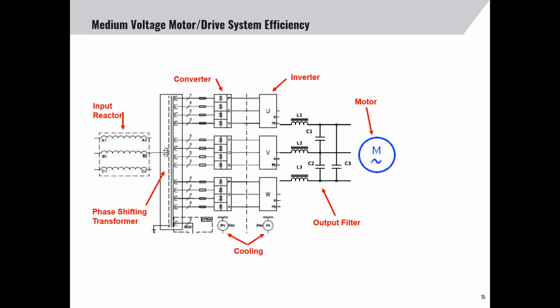Unlike motors, most adjustable speed drives are mounted indoors. Like motors, most of the efficiency losses are in the form of heat. Therefore, the heat loss from your adjustable speed drive must be dealt with to keep the equipment from overheating and potentially failing. Some of the common methods to deal with this heat include using water cooling, air conditioning, or large heat exchangers. Now, each of these methods has advantages and disadvantages, but they all require power to operate and thus should be considered in the total life cycle costs. There are some manufacturers offering outdoor drive solutions that eliminate that additional expense, as well as eliminating unreliable air conditioners and/or water cooling systems.